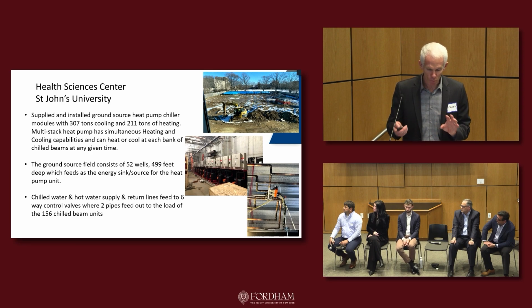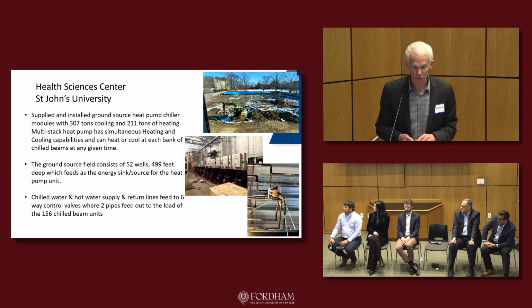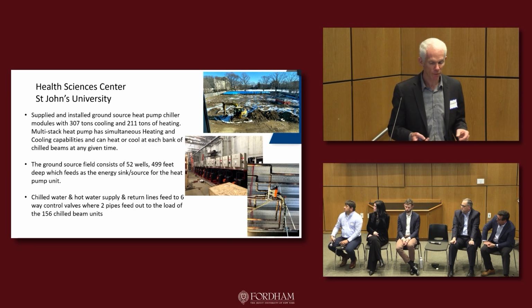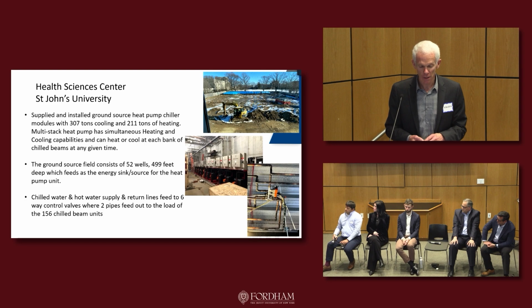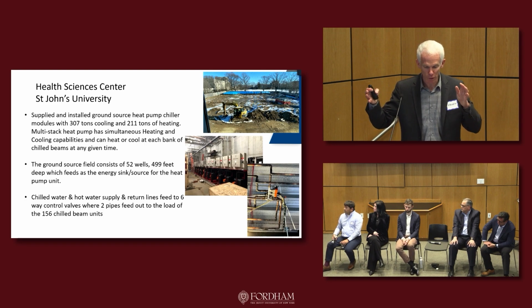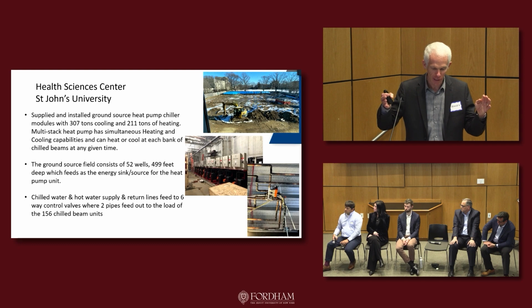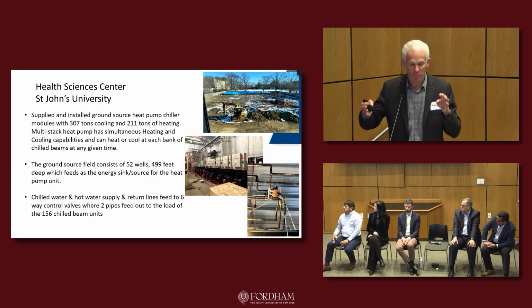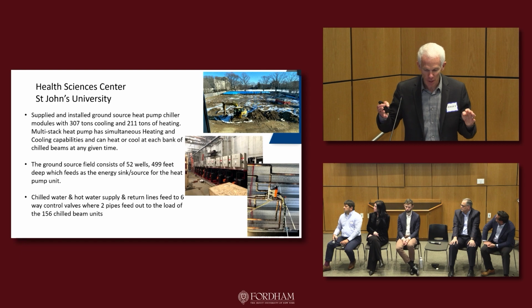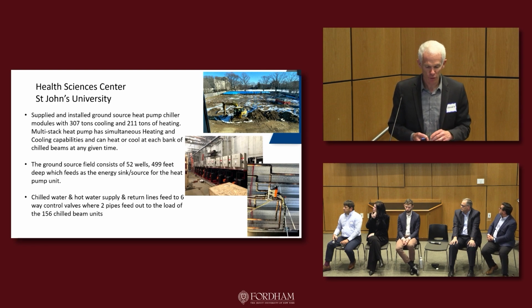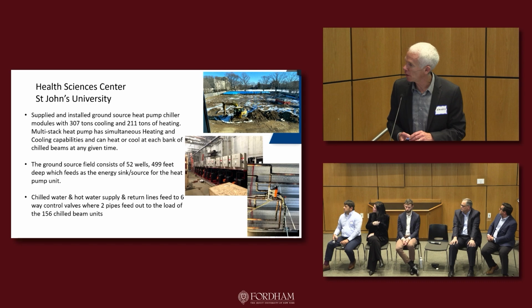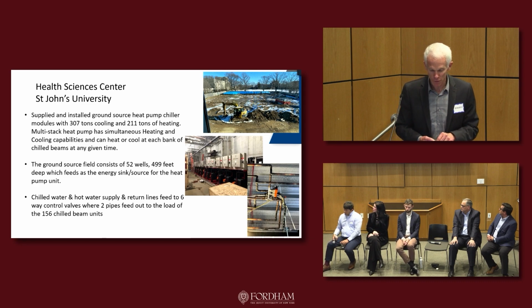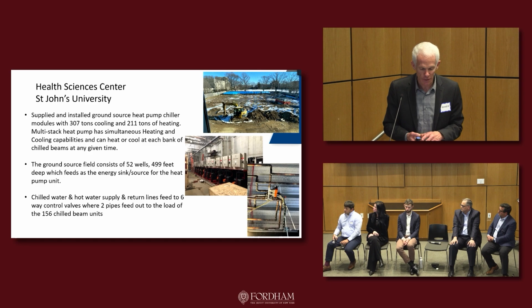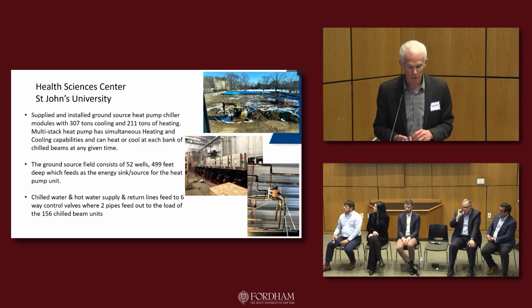We were involved in supplying and installing ground source heat pump chiller modules, 307 tons of cooling, 211 tons of heating. They're basically multi-stack type modular units that allow simultaneous heating and cooling capabilities in terms of being able to heat and cool each module, if you will, and then it feeds chilled beams, which I'll speak to in a second, at any given time. The ground source system field consists of 52 wells, 499 feet deep, which feeds and acts as the energy sink and source for the heat pump unit.